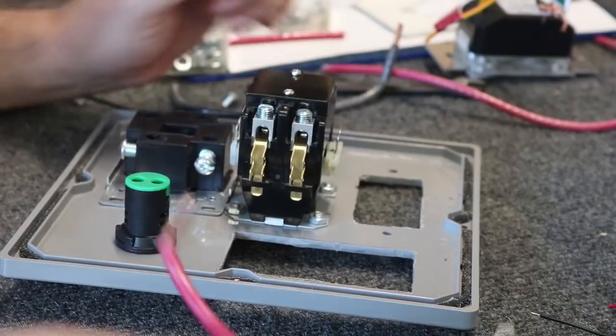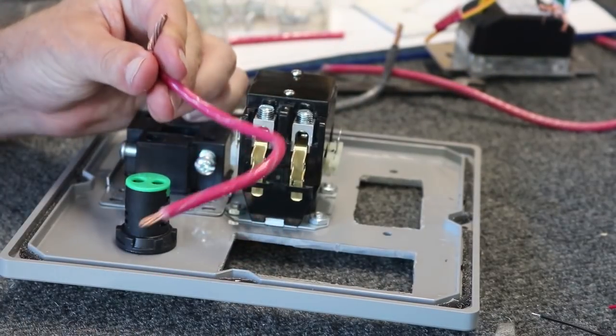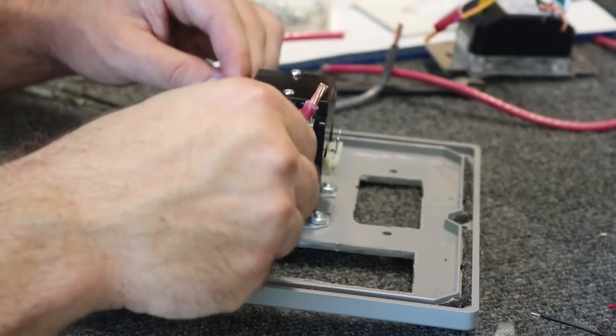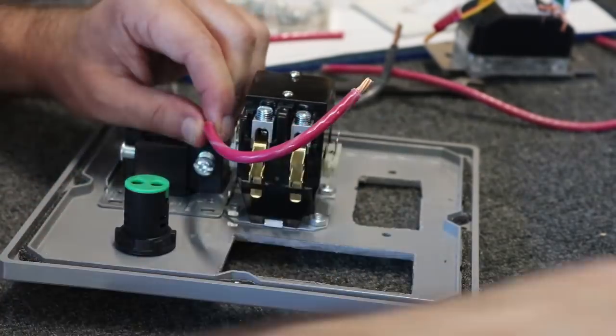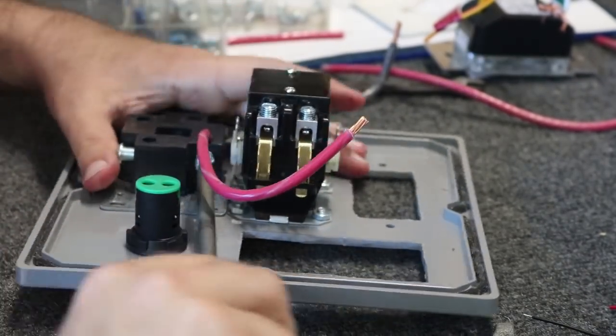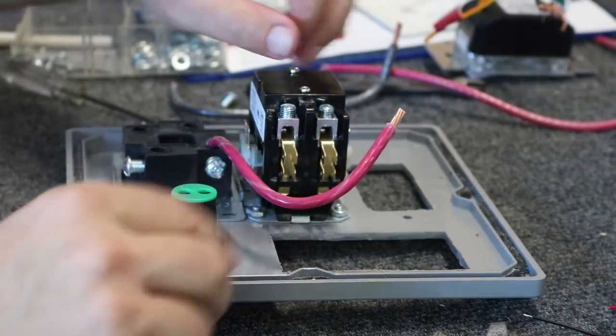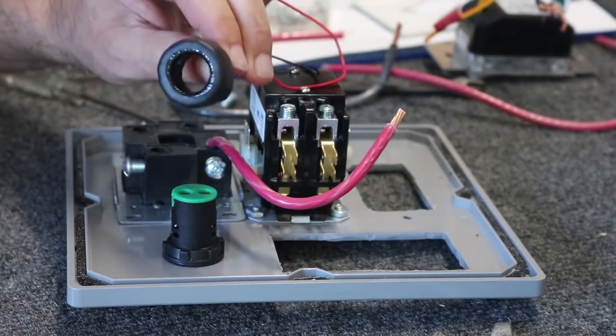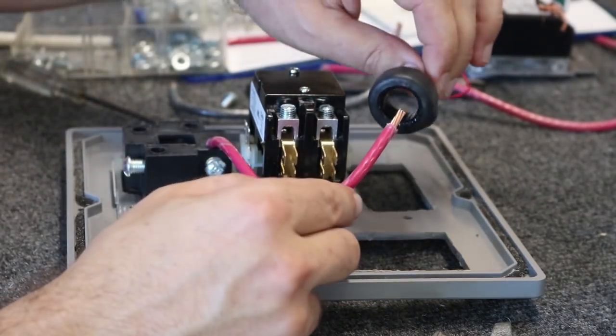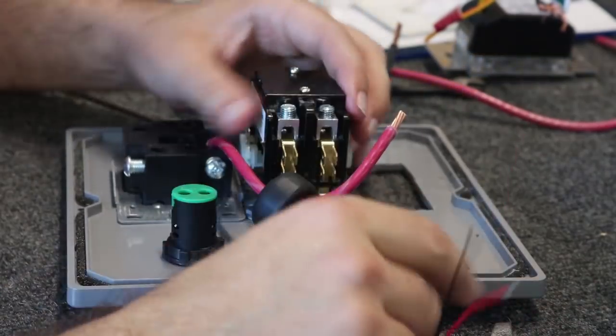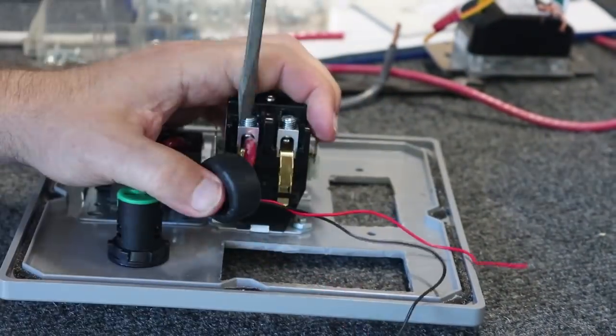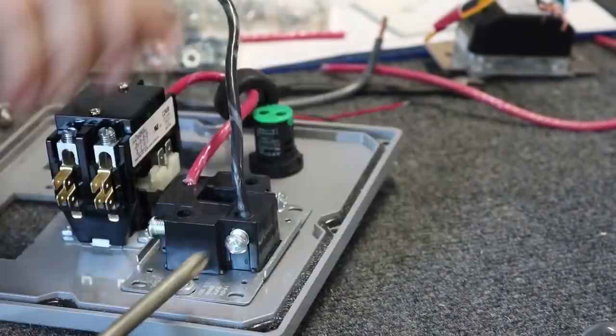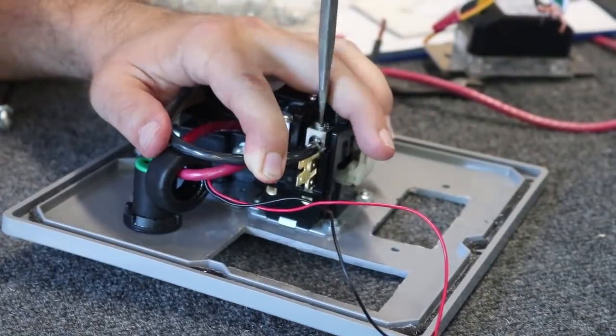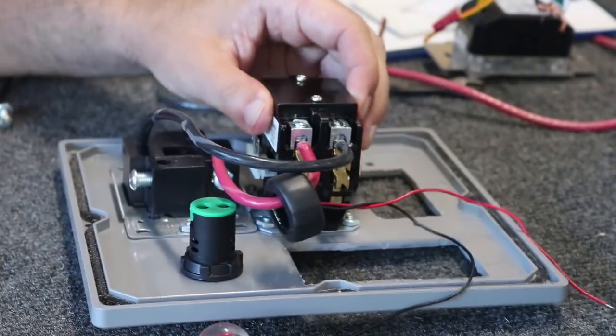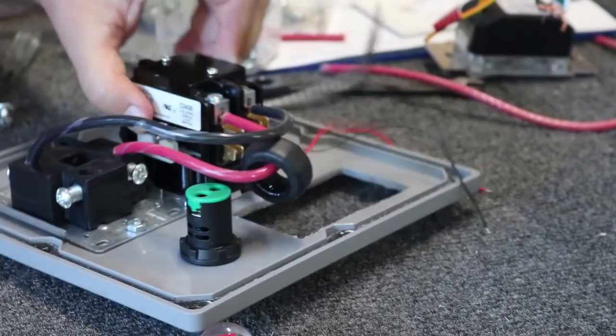With the contactor and the NEMA 14-50 electric outlet screwed to this faceplate panel, I can start wiring it up. Here I'm using some heavy 6-gauge wire, and on this red hot wire I'm going to slide the current transducer for the display so we can measure current over the wire before connecting it up. And then after that, the other hot lead, the black wire between the NEMA 14-50 and the input side of the contactor.